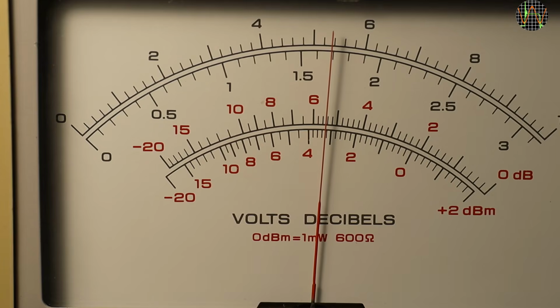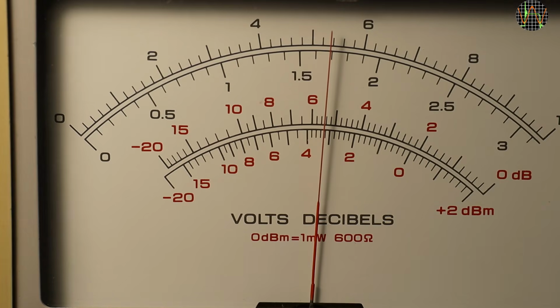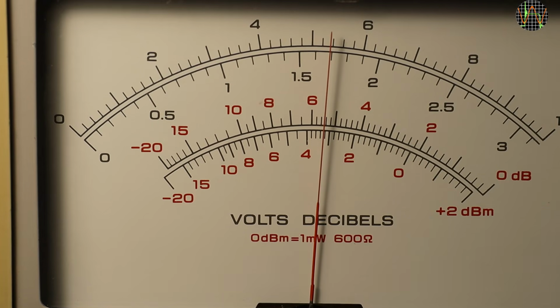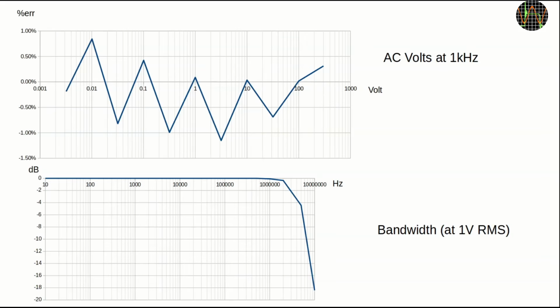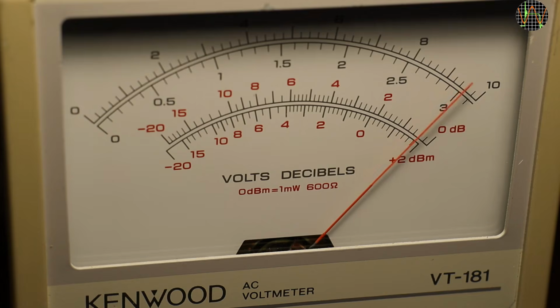Just to be clear that the VT-181 is an averaging meter, not true RMS. Here I feed it a 5 volt RMS signal, but it's a square wave, not sinusoidal. And as any averaging meter, the VT-181 shows a 1.11 times too high value for square waves. 5.5 and a bit volts instead of the 5 volts a true RMS meter would show. After calibration, the error at 1 kHz was within 1%, which is certainly better than the max 3% allowed. The bandwidth was also well beyond the specified 1 MHz. But the claimed 5 Hz are not really usable.